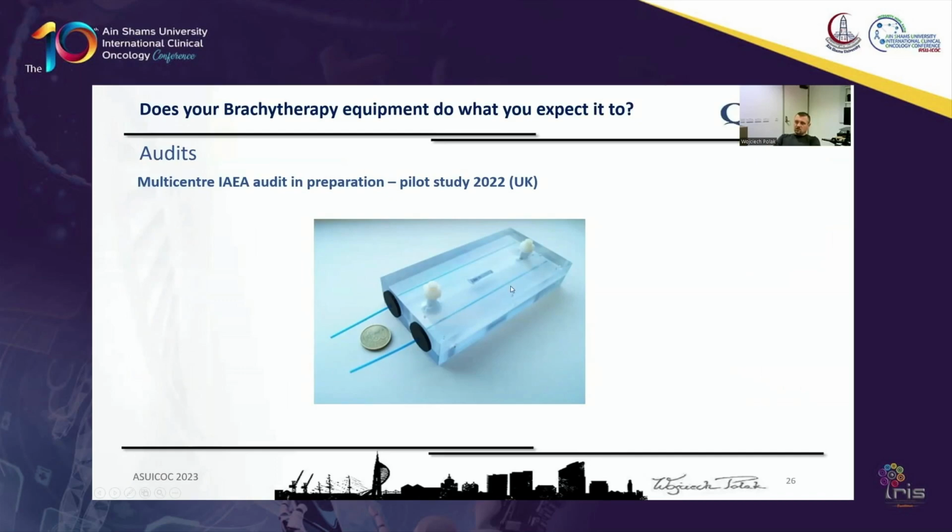There are a number of sources along the catheter to create a fairly uniform distribution in the center, with a glass rod dosimeter to check the dose. And there's also a place for film to check the source positions in the catheter.